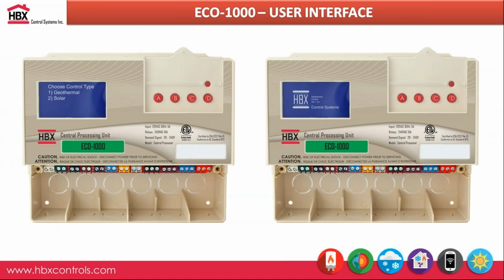In terms of the user interface, when you power up the Eco 1000 for the very first time, it's going to give you the version number. In terms of the software, this can always be updated. So if you have an older version, you can always send it to us for updating purposes. That's not a problem. But we haven't really updated the software since 2014, because I think we've got all the components that you really need for a geothermal system onto the controller itself. So when you power up the Eco 1000, it'll also ask you to choose your control type.